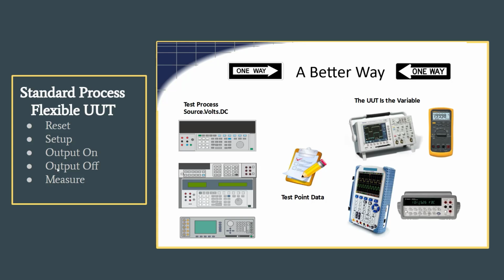The flexibility comes from this: instead of making a driver for our calibrator or our reference standard and making those interchangeable, what we did in Metrology.net is we made the unit under test flexible. By making the unit under test flexible, I only have to deal with 5 major things: the reset of the flexible unit under test, the setup of it, output on, output off, and take a measurement. That covers about 95% of all the calibrations that we do.